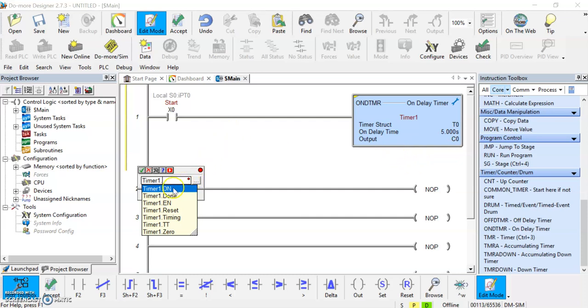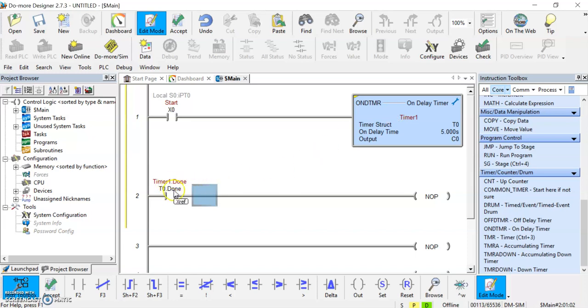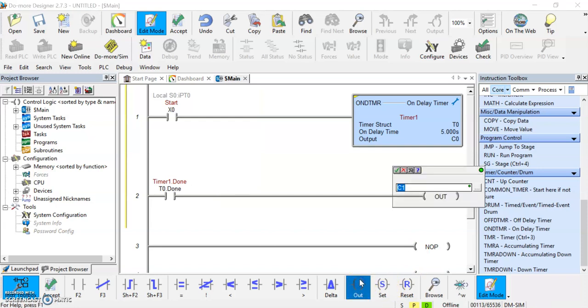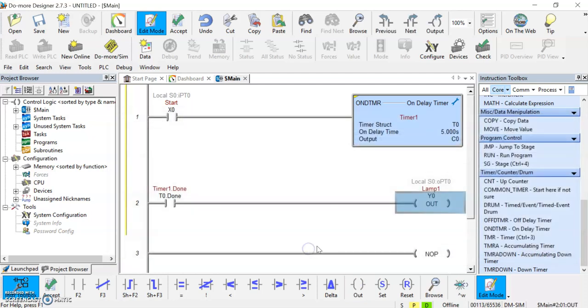Now here what we're going to use is the done bit. It's just easier. I'm going to go with that one here. And what that'll do is when this goes true here, this will start timing. And then at the end of that timing cycle, this will go true and activate whatever I have over here. So now I'm just going to go over here and I'm going to put an output here. And I'm going to call that lamp one. I don't like that, capital A. Lamp one. And then it's going to obviously want me to associate that with something. And I'm just going to call that Y0 for my simulator. And now I have a basic timing function.